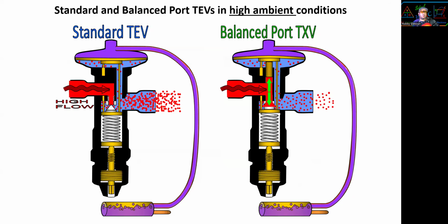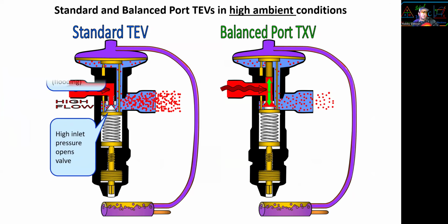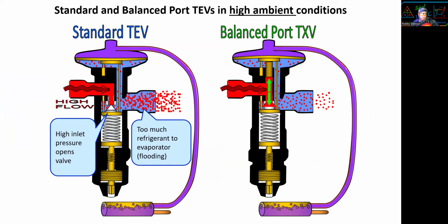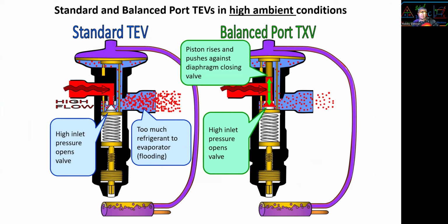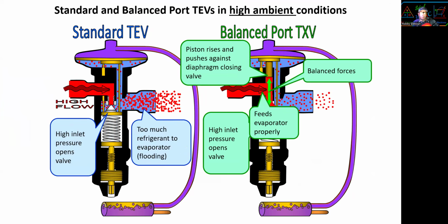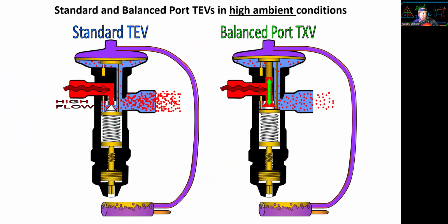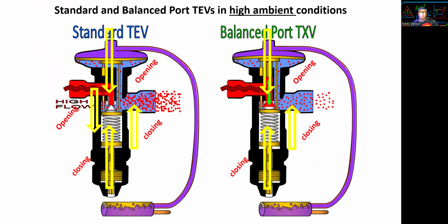And now let's talk about standard TXV versus balanced port TXV. With the standard, high inlet pressure opens the valve, too much refrigerant, flooding. High inlet pressure opens the valve, the piston rises and pushes against the diaphragm. It's a balanced port, it feeds the evaporator properly. So instead of having open, open, close, and close, now we only have three: open, close, and close. We eliminated the high side.